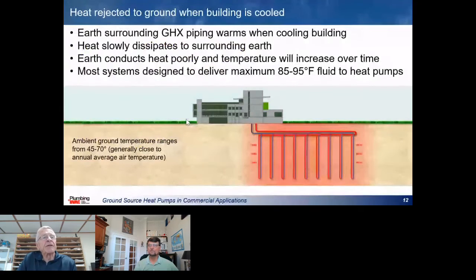Ground source system is different. Basically, what you're doing is building an energy storage tank in the ground. And the ground itself is not really a great conductor of heat, but if you install enough pipe in there and you circulate fluid through it, you change the temperature of that fluid, you can move that energy around. You're going to gradually, by the end of the year, at the end of the summer, warm up that fluid probably to around 80 to 90, 95 degrees Fahrenheit. And that's the high maximum temperature that most water source heat pumps are comfortable operating at a reasonable efficiency.